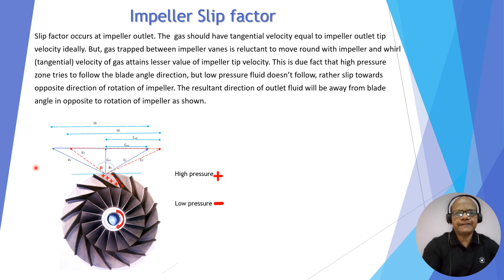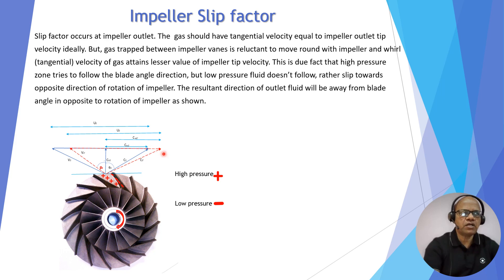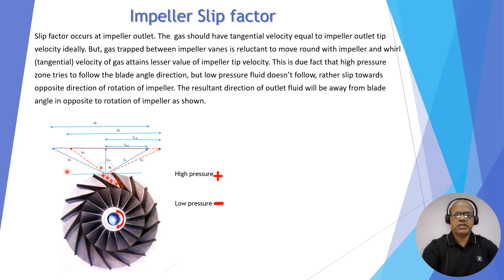Now let us understand the slip factor. Because of the slip, the actual whirl component is reduced — instead of the ideal whirl component cw2-dash, the actual tangential or whirl component is smaller. That is why, due to slip, the performance of the compressor is deteriorated and the discharge pressure is lowered.